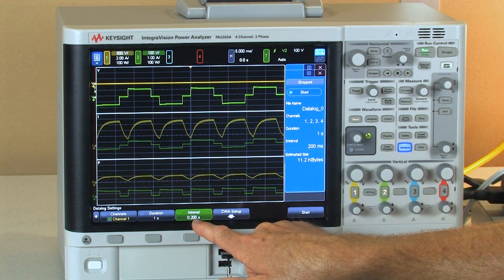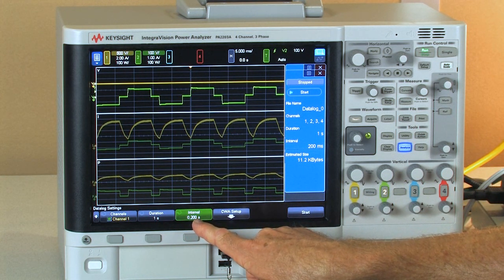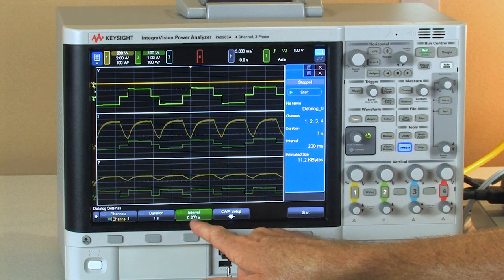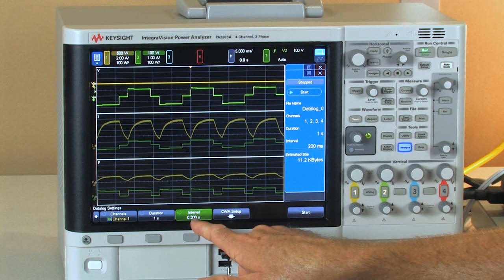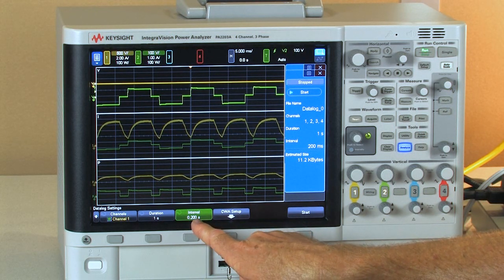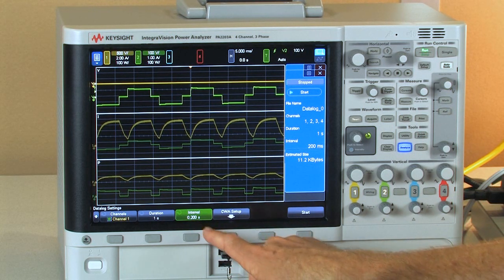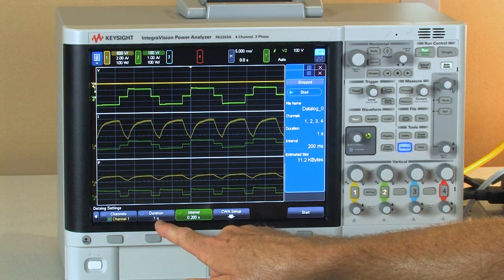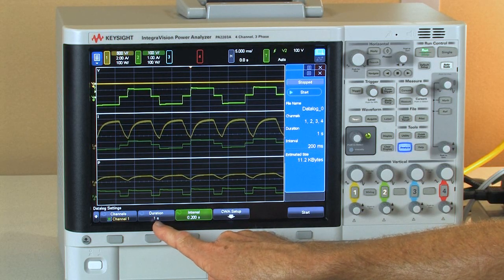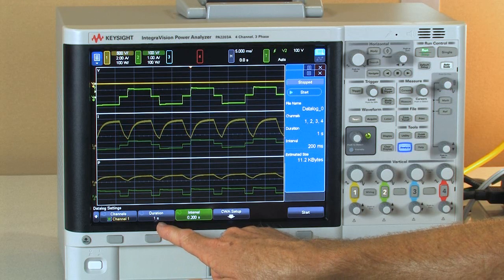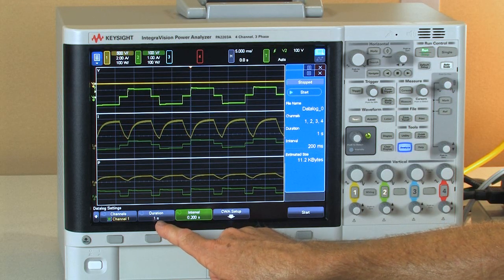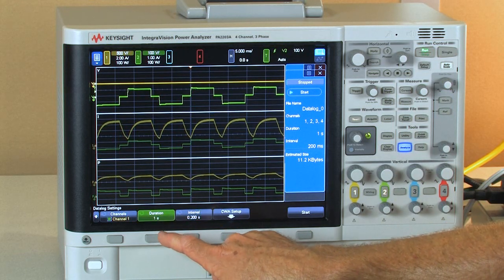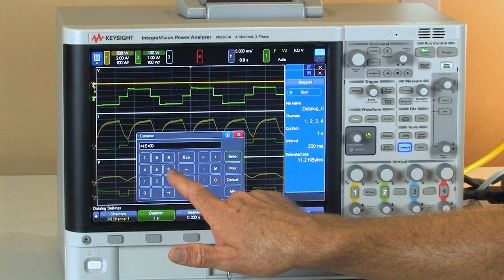By selecting 200 milliseconds or higher we actually get some additional measurements. We get the total harmonic distortion measurement as well as an efficiency measurement logged to our data file. Our duration can be as short as one second or as long as 365 days. I'm going to choose 60 seconds.